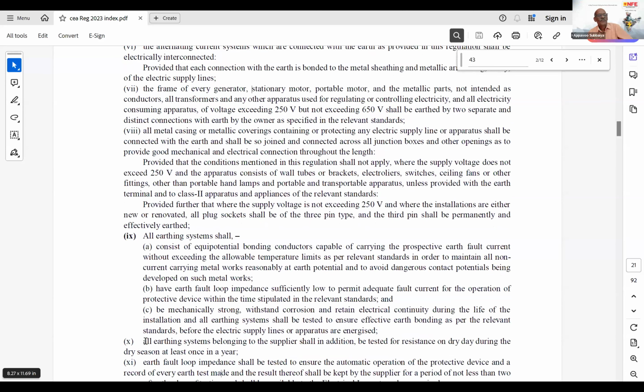The thing is, earth loop impedance and earth resistance should not be confused by people. As expressed earlier, earth loop impedance is applicable for the LV installation, where the major earth fault current seeks a path through the protective earthing terminal and earthing conductors. So the part of earth electrodes doesn't come into the picture. The earth electrode has a role, but only for referencing the system to earth.